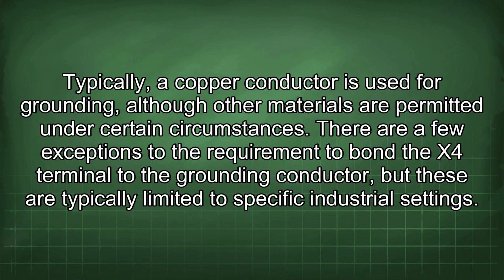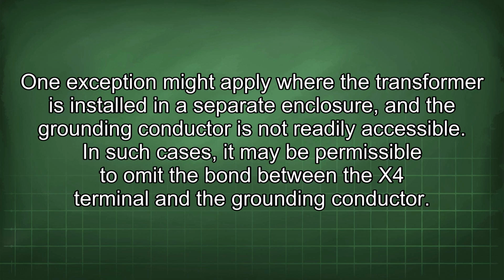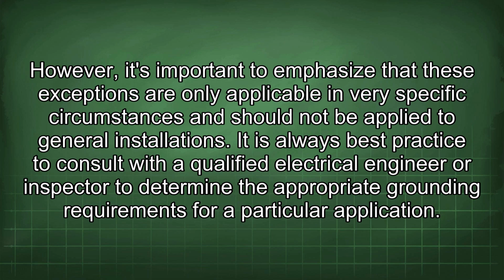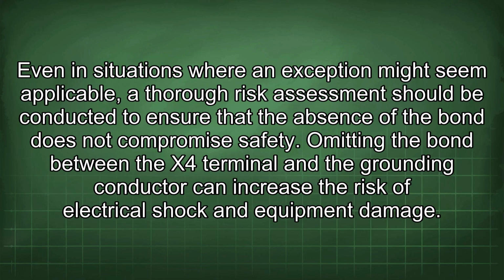There are a few exceptions to the requirement to bond the X4 terminal to the grounding conductor, but these are typically limited to specific industrial settings. One exception might apply where the transformer is installed in a separate enclosure and the grounding conductor is not readily accessible. In such cases, it may be permissible to omit the bond between the X4 terminal and the grounding conductor. However, it's important to emphasize that these exceptions are only applicable in very specific circumstances and should not be applied to general installations. It is always best practice to consult with a qualified electrical engineer or inspector to determine the appropriate grounding requirements for a particular application. Even in situations where an exception might seem applicable, a thorough risk assessment should be conducted to ensure that the absence of the bond does not compromise safety.